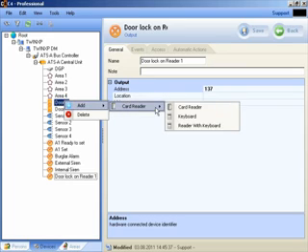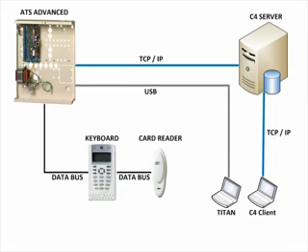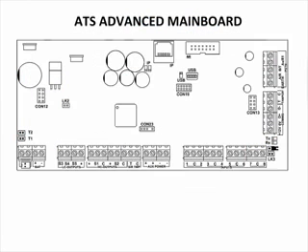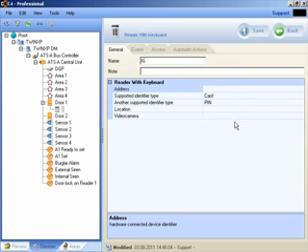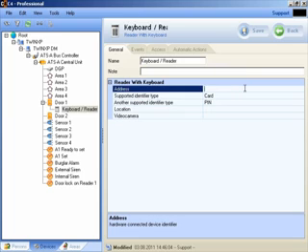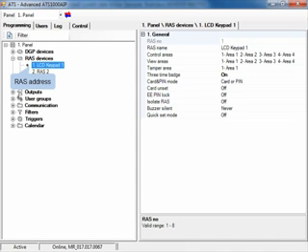Under doors, add keyboard or card reader, depending on the configuration. RAS devices are communicating with Central Unit using RS485 system databus. RS485 system databus connects directly to the main board. Again, keyboard and reader address can be found in Titan.